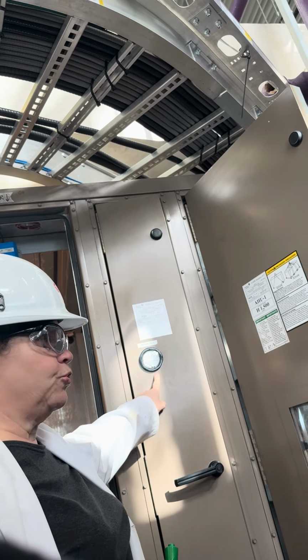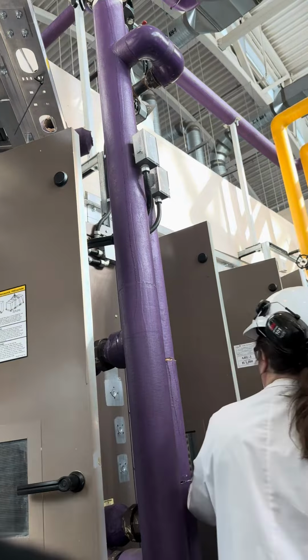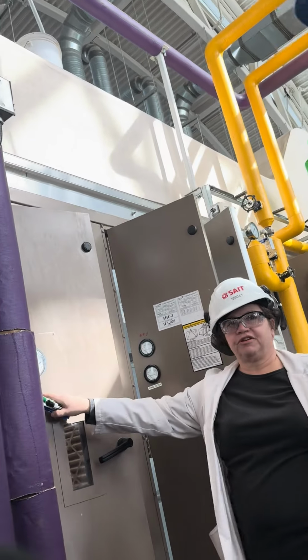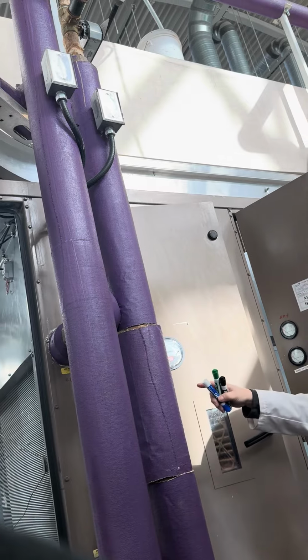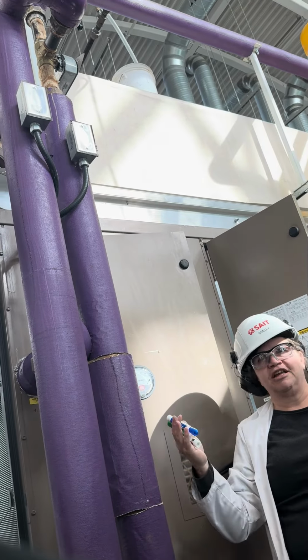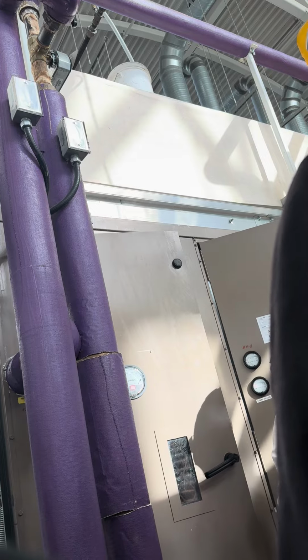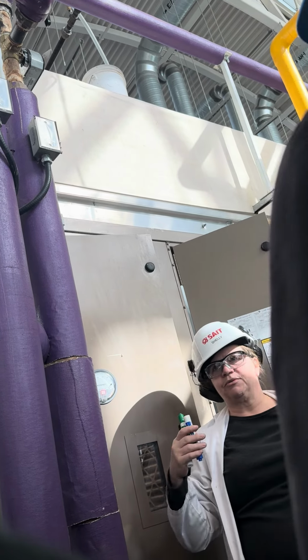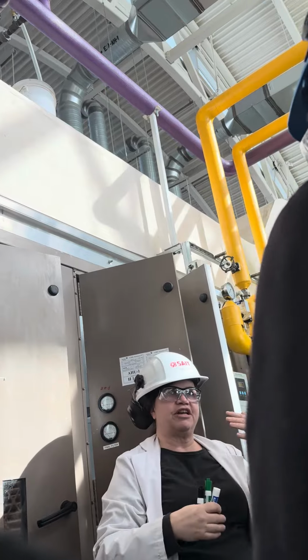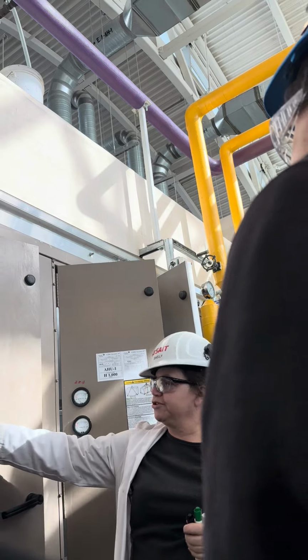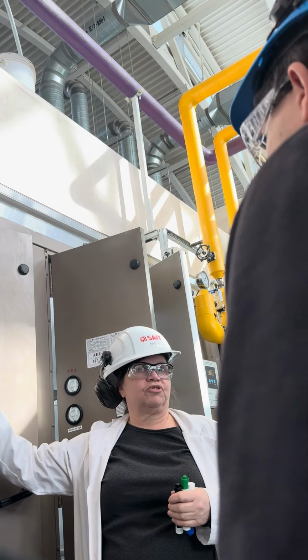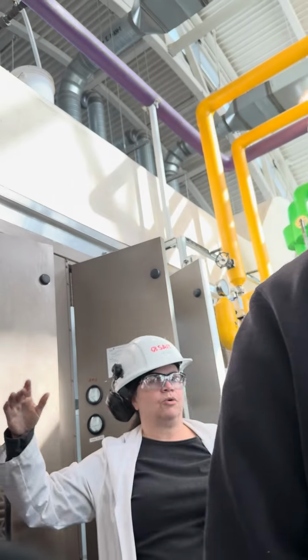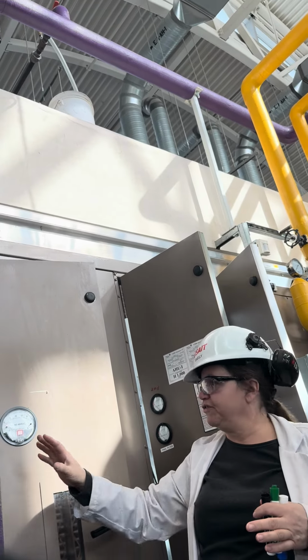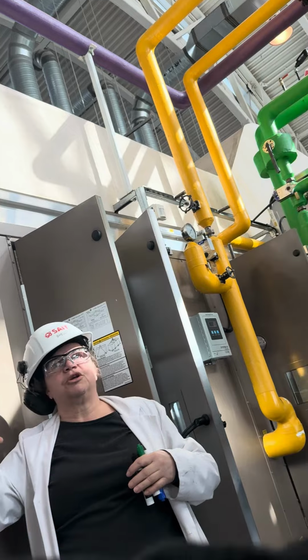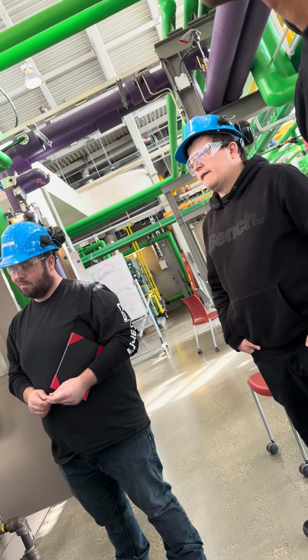We have pressure before the filter, and we have pressure after the filter. Okay, so now we know how much airflow is coming through our filters, which gives us an idea of how often they need to be changed. Generally, if you're going to work at a place, they already have kind of a schedule. They know every 4 months we have to replace them, that sort of thing. But we're also going to make sure that during the summer, when we had all that extra smoke and all that extra particulate, the filters were plugging up a lot faster than you would normally expect. So that's why we look at our pre and post filter.